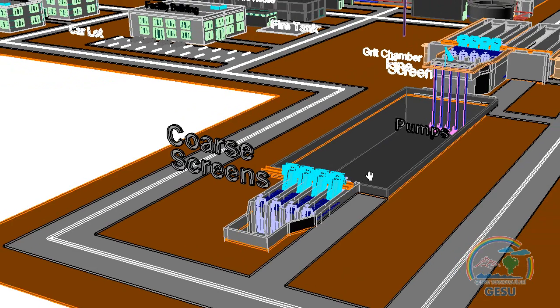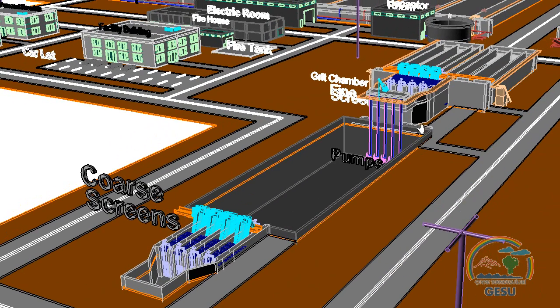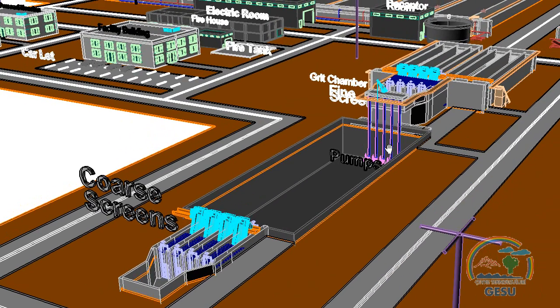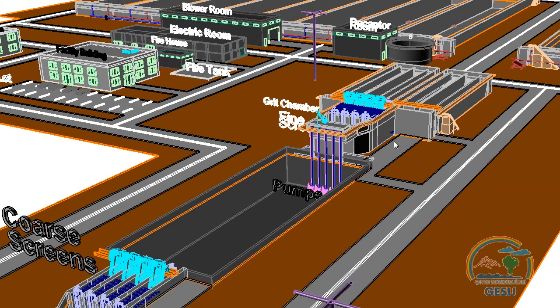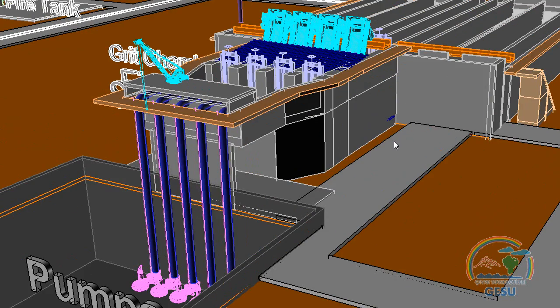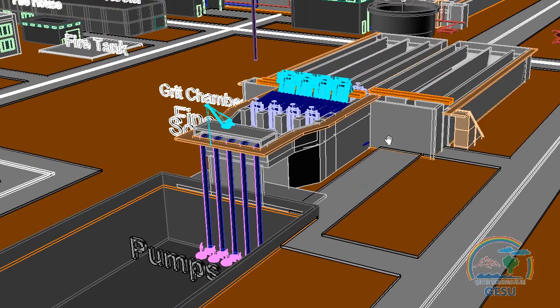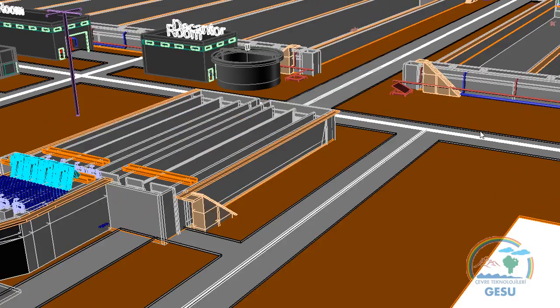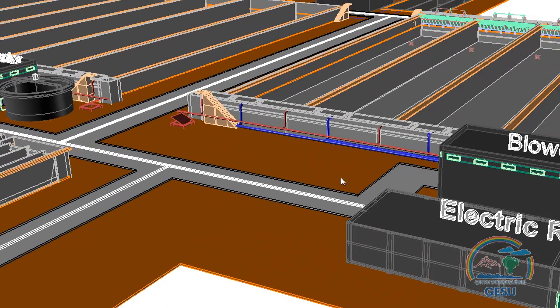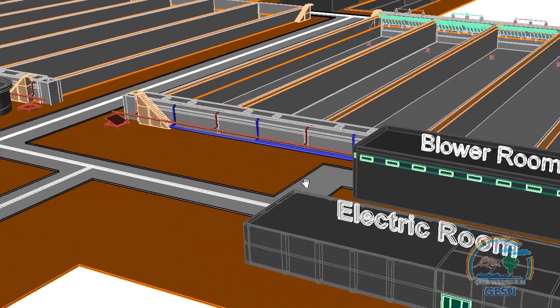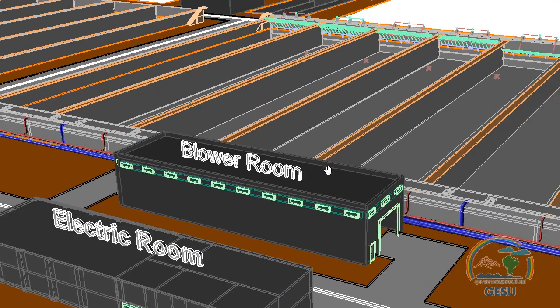In the pre-treatment unit, coarse screens, inlet pump station, fine screens, and grit chamber units have a capacity of 120,000 cubic meters per day. Eight SBR tanks designed for the first step can treat 60,000 cubic meters per day of wastewater.